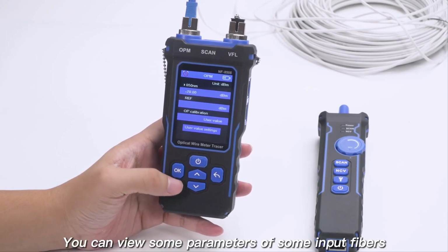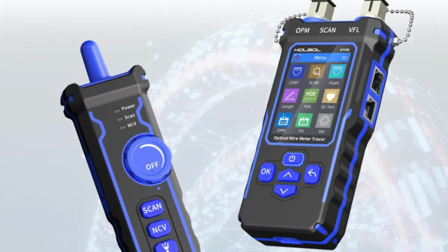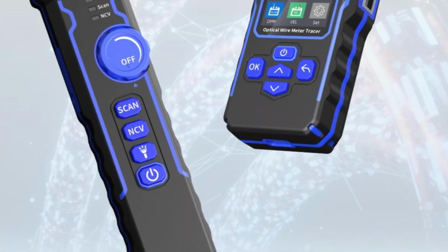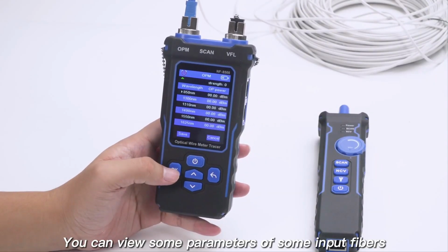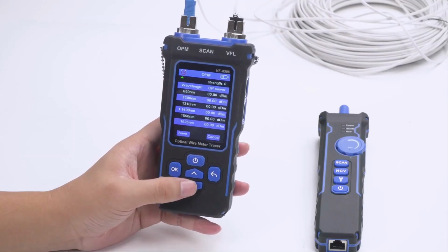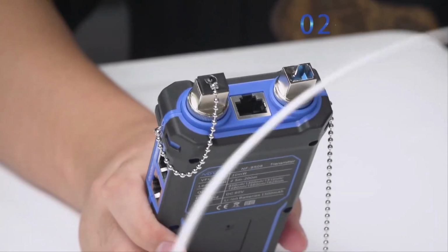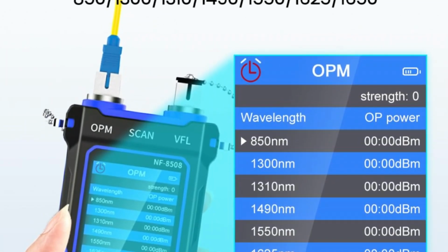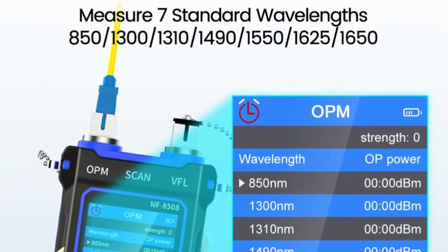Its optical power meter supports 7 standard wavelengths: 850/1300/1310/1490/1550/1625/1650 nm, with a power detection range of -70 to +10 dBm, while the visual fault locator provides fast and slow flashing modes with high precision.